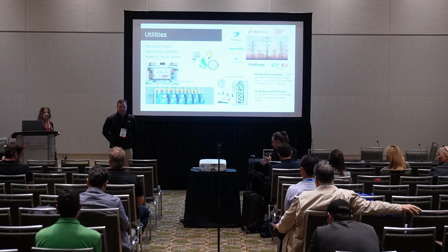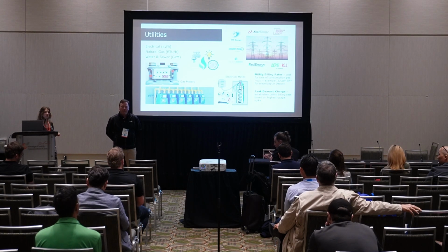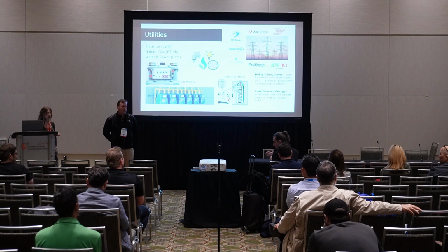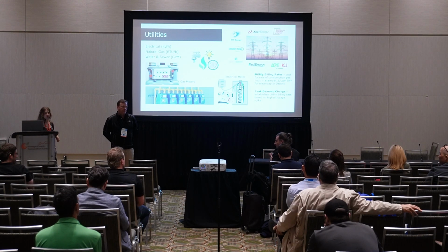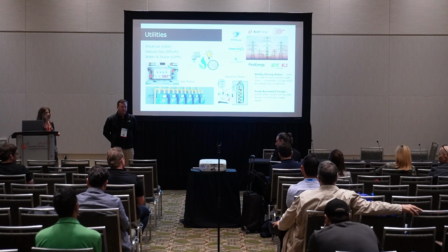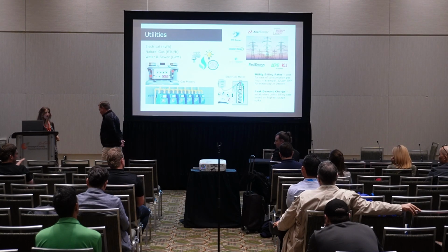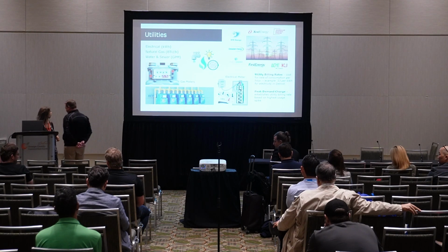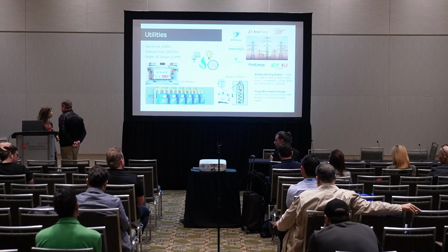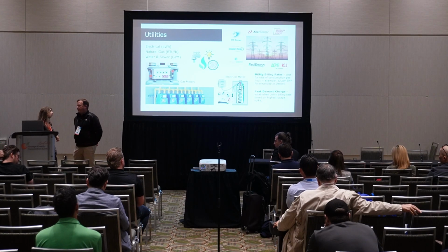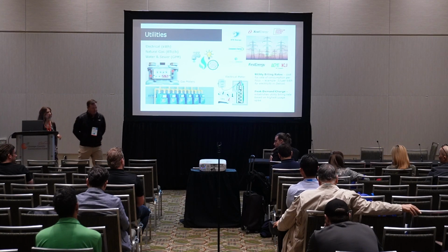Water pump speed drives, or capping the chiller output, right? A lot of chillers will let you cap the reset on it so you can't go to full capacity. That's actually more effective than set point relaxing. The set point relaxing is less impactful in terms of occupant experience, but often you're having to do a quick response for load shedding because you've got maybe 10 minutes to respond before you incur that peak.